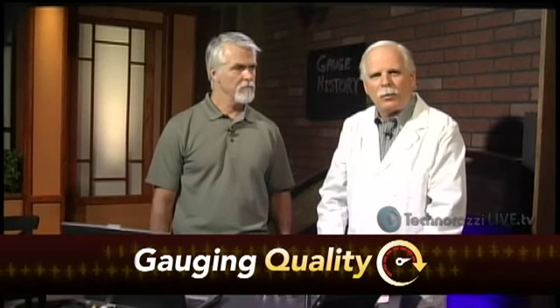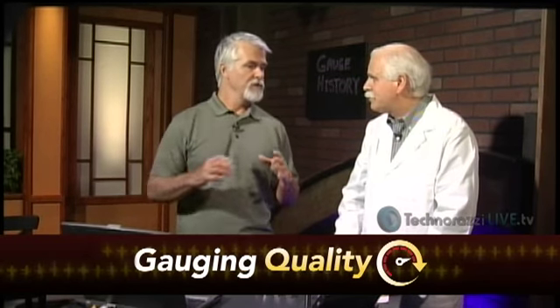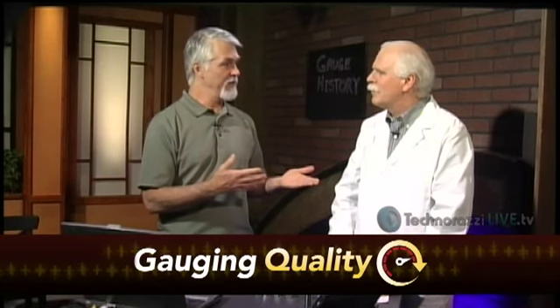If I had gone in cold, if I didn't know the scale and just saw the limitation, don't use above a certain range, and I tried that, I would think the other lab had done something wrong, when really that is just the situation. And also by leaving that note, if they were to change calibration labs, the next person to calibrate that gauge would see your note, and that would be kind of a heads up for them.